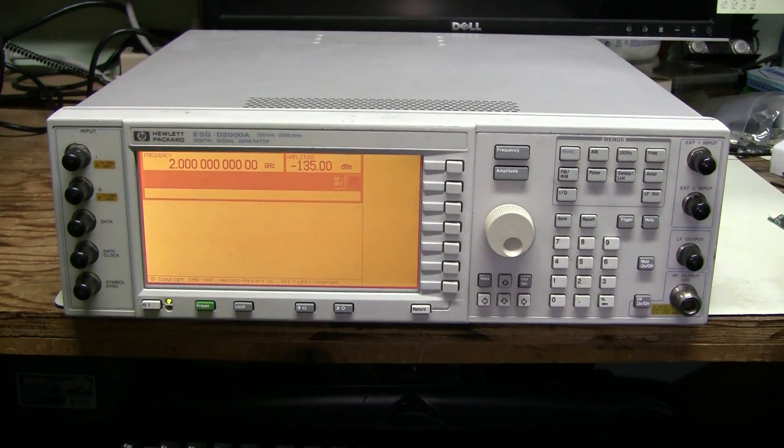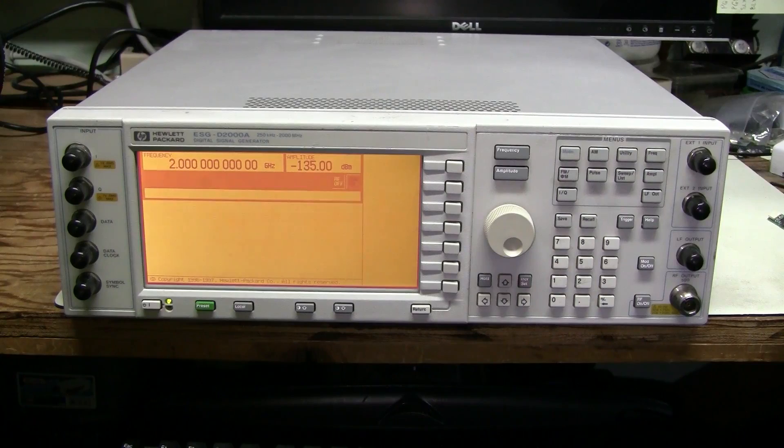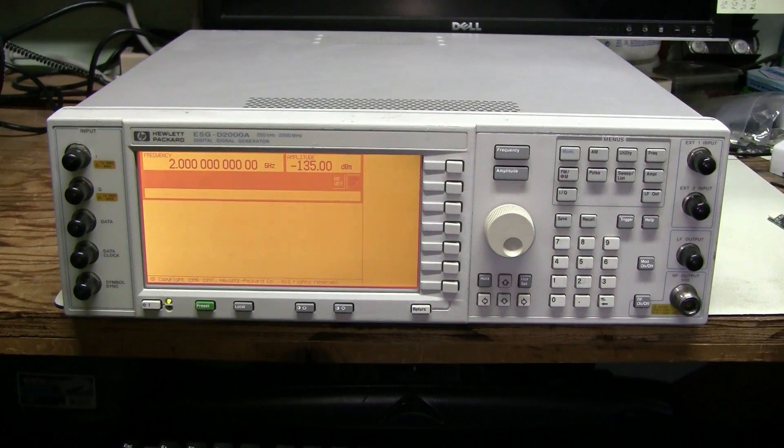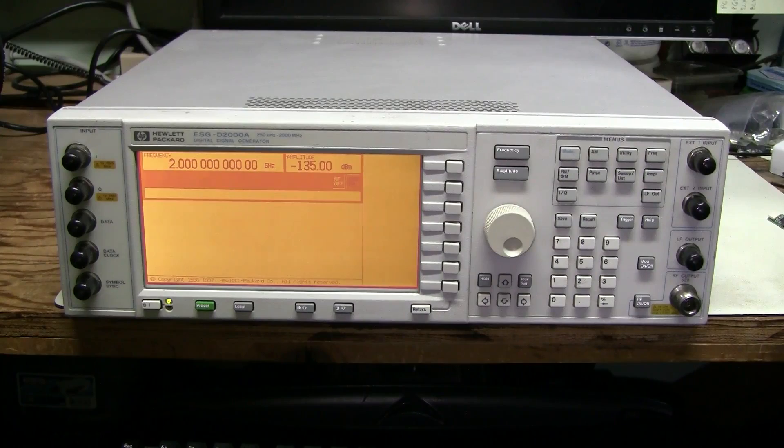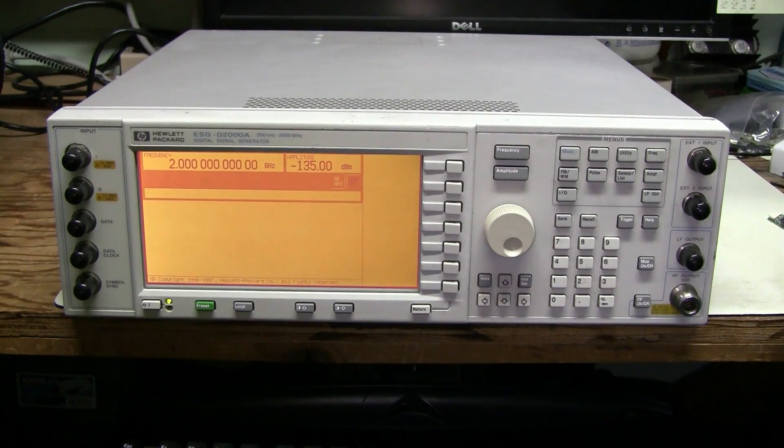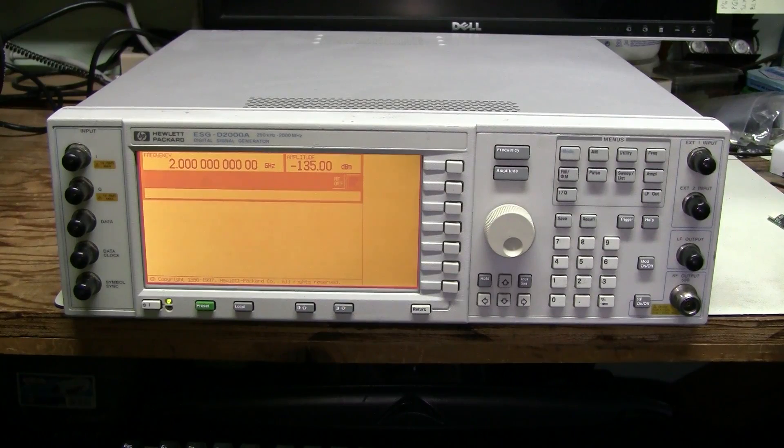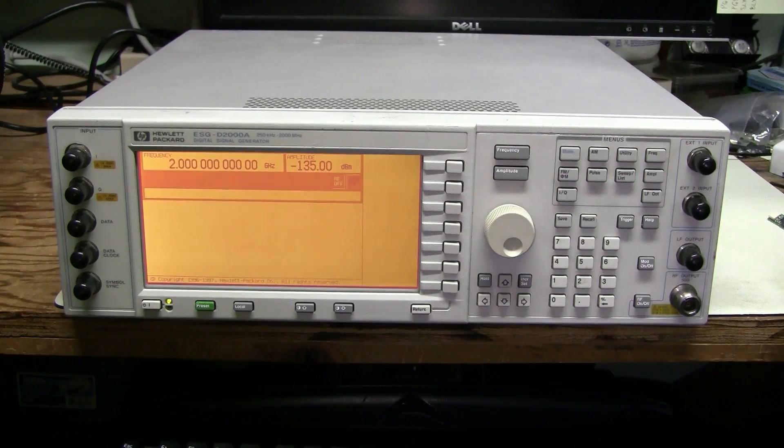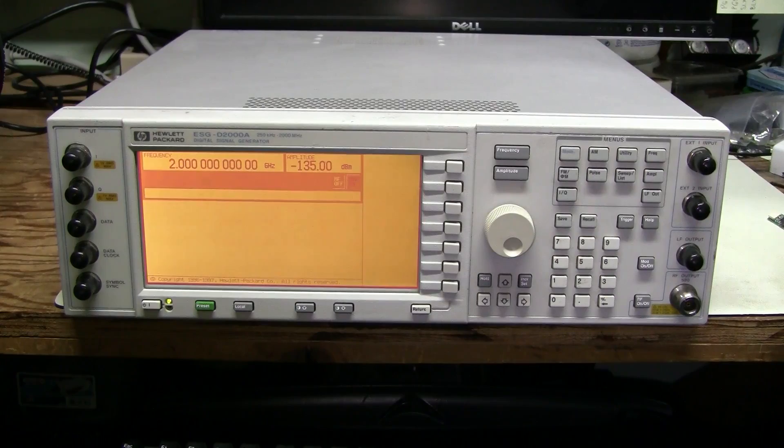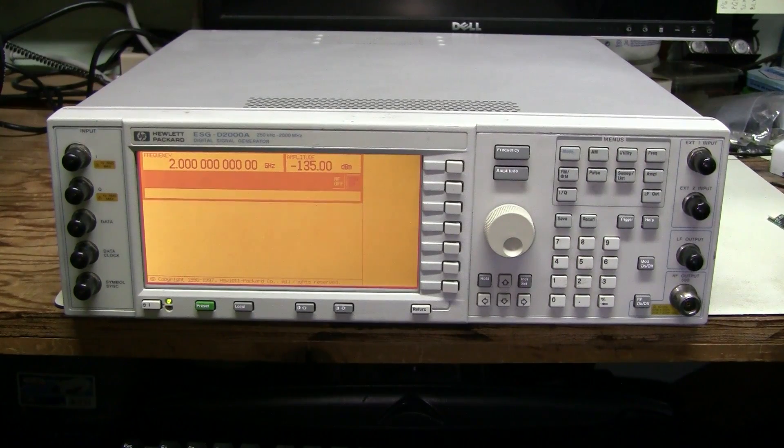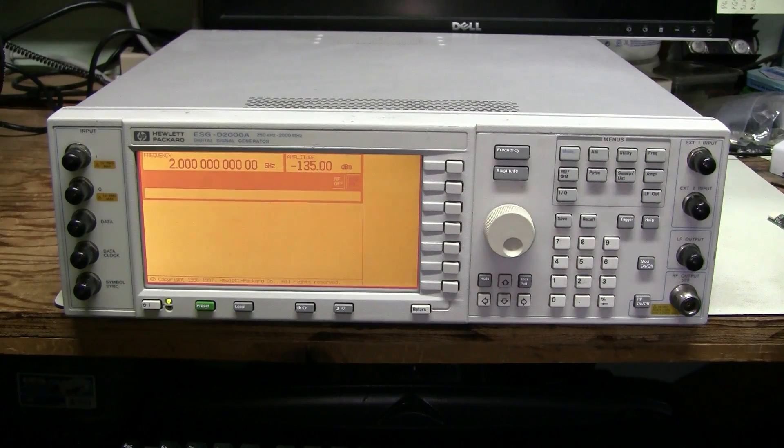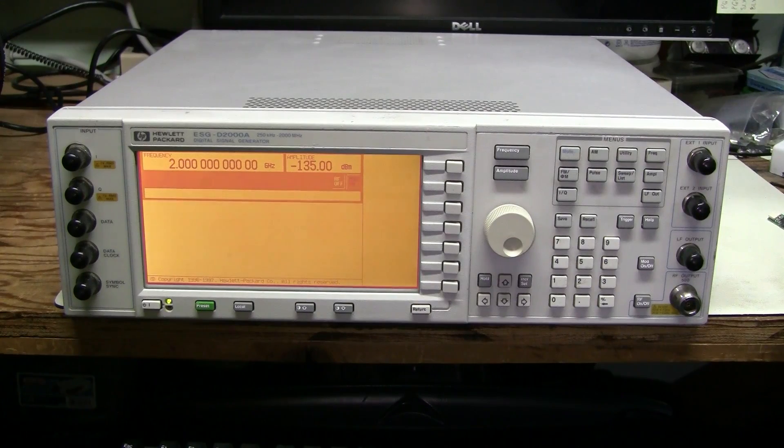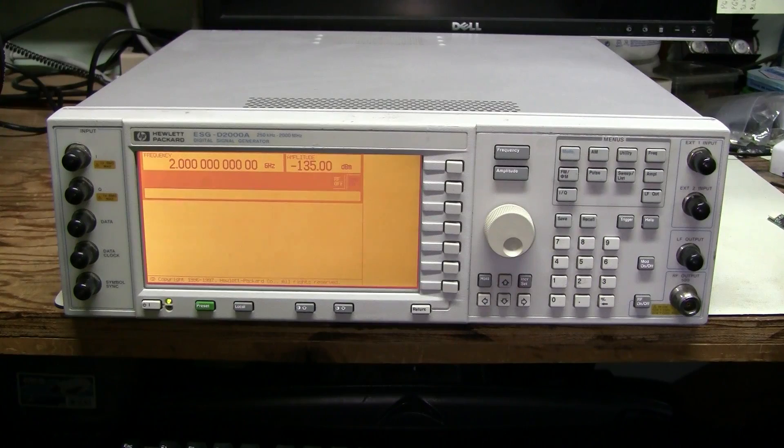I borrowed the attenuator and the amplifier board from another similar instrument I have. And the modules are interchangeable. And I managed to repair the LCD screen to some extent. I had to replace both the front and back polarizer films. I don't know what happened to them, but they looked as if they have been fried or something. All cracked and bubbled.